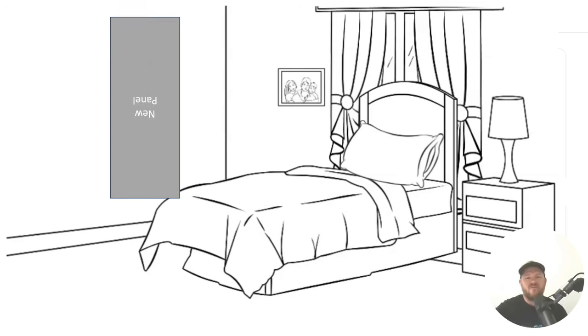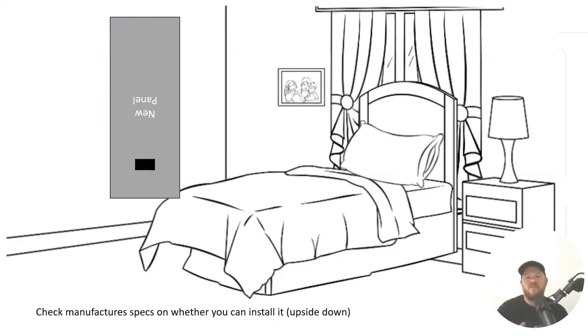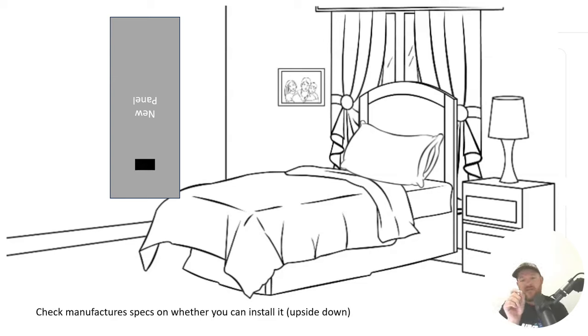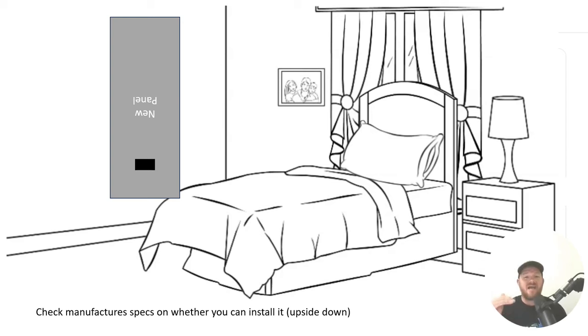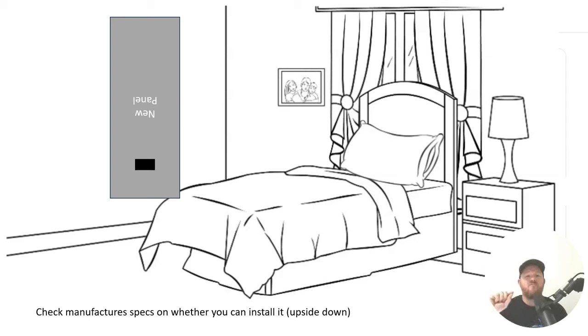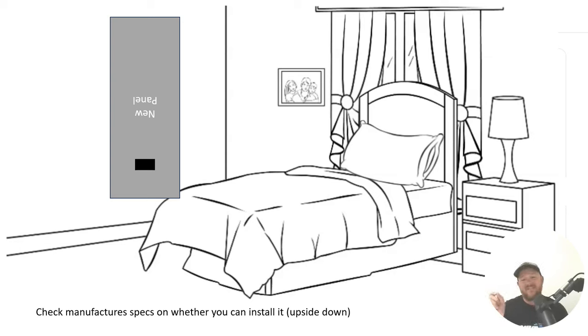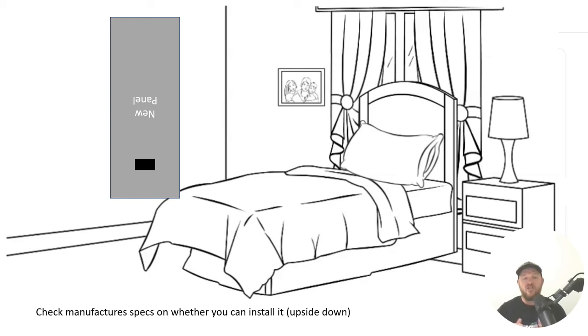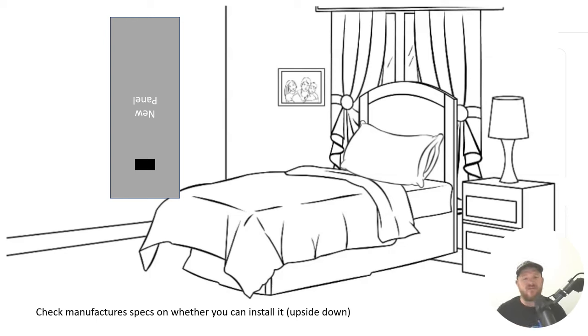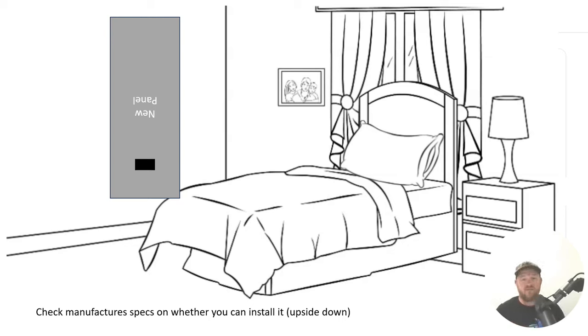So you decide that you're going to flip this panel upside down and put your main breaker on the bottom. Not a problem, as long as the breaker goes from left to right, then you're okay. It cannot ever be installed that if it's an up and down breaker, that it's in the off position while it's up. But if you have a side to side breaker, you can likely flip that panel upside down and use it with the main breaker on the bottom. But the question is, am I good to go? Do I have any other considerations for this specific code? And the answer is you do. We are not just in the clear.